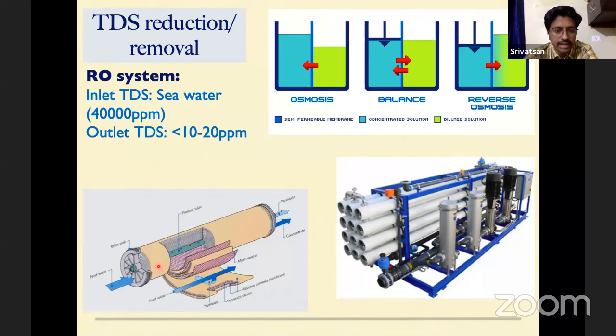Then permeate gets collected in the central tube and permeate is taken out. Whatever water doesn't pass through the membrane gets concentrated on the other side. That is called RO reject or brine. This is a typical RO skid wherein we find here the high pressure pump for producing the pressure higher than the osmotic pressure.